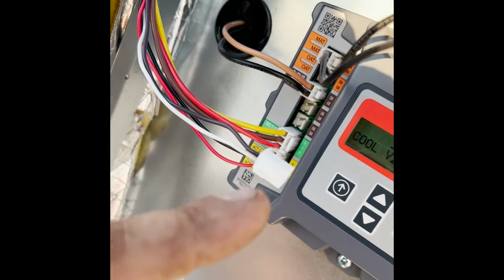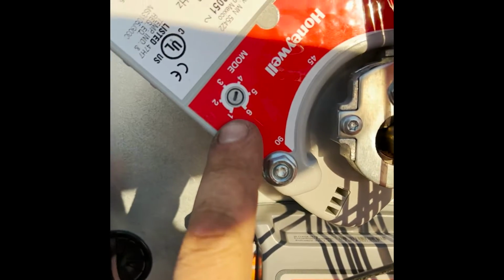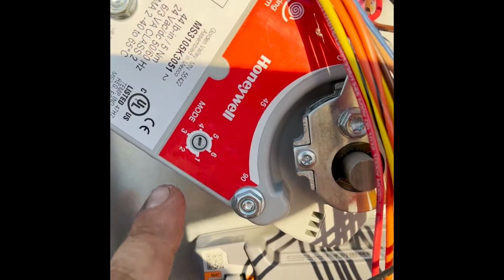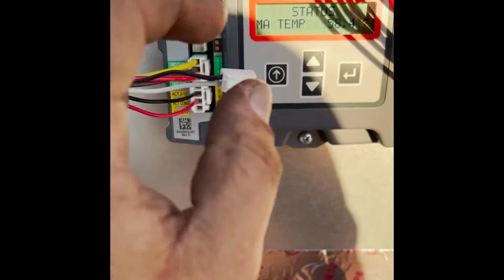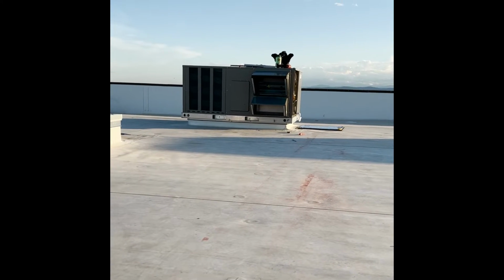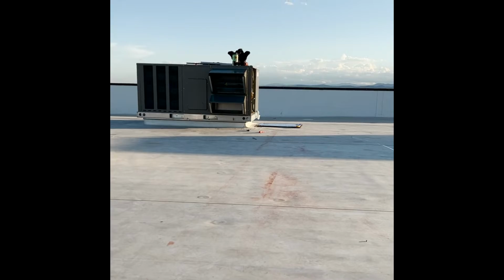The other accessory here, we're on the unit next door. We're doing a little bit of movie magic. Okay. 8.6 microfarads. And that's reading between these two bad boys coming off of this in the same situation. So we're back in protocol 1, which used to say a voltage, now it says addresses or whatever. Protocol 1, we can still read our stuff here, and I have microfarads now on this same plug. On our unit in question, I have 0.02 ohms, and I think it's basically trying to short out the board. It's going into protection mode and stopping putting voltage out on those terminals. So I think the part that's actually bad is this.